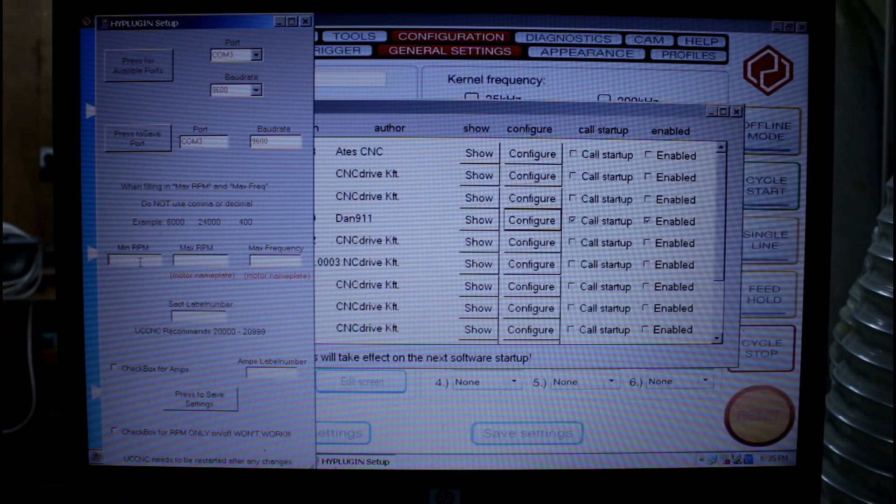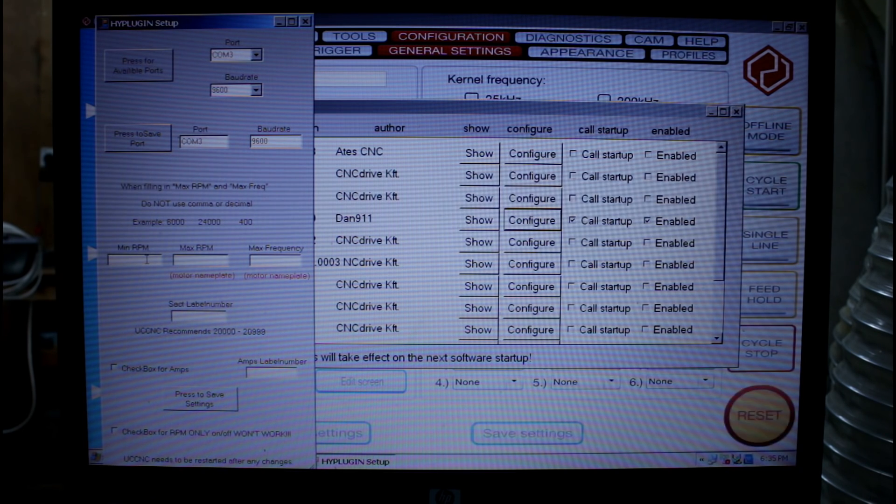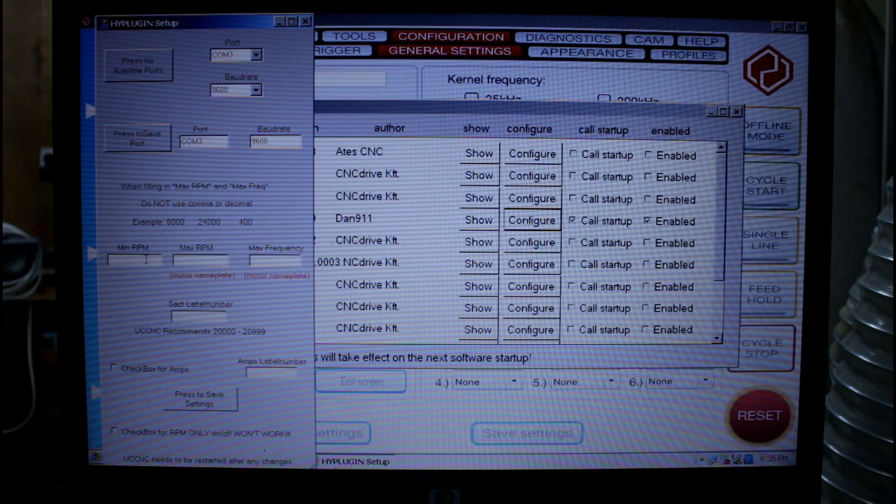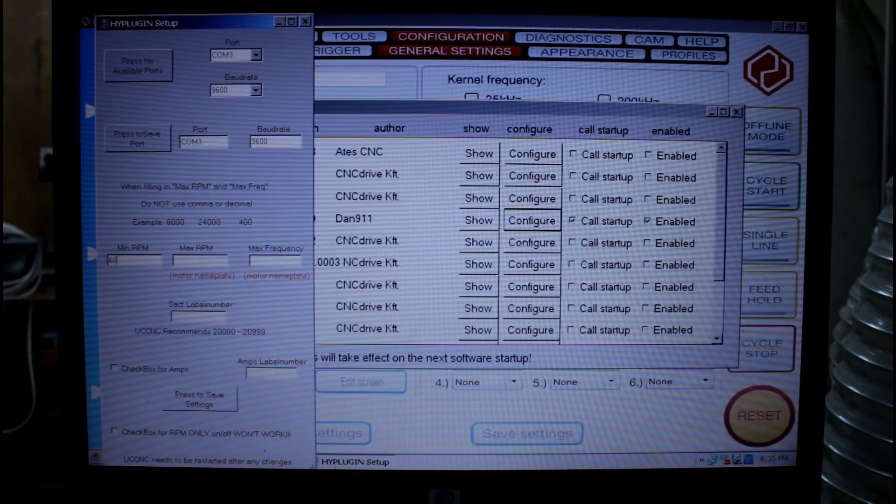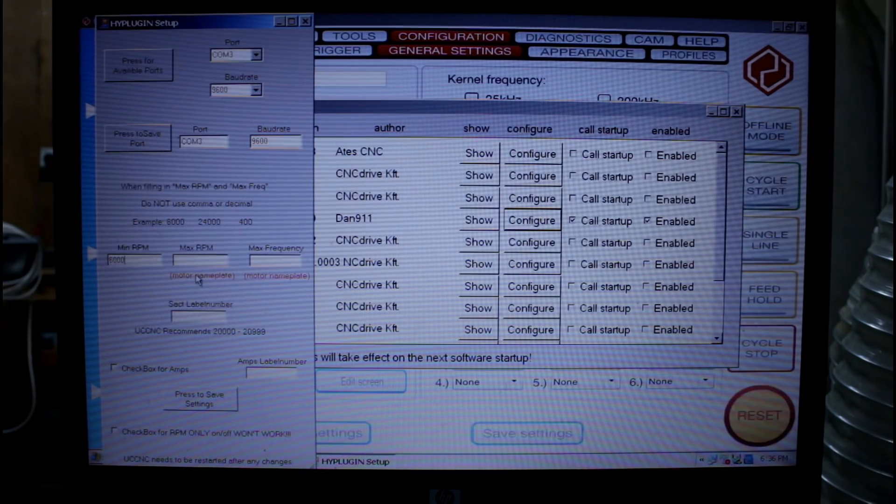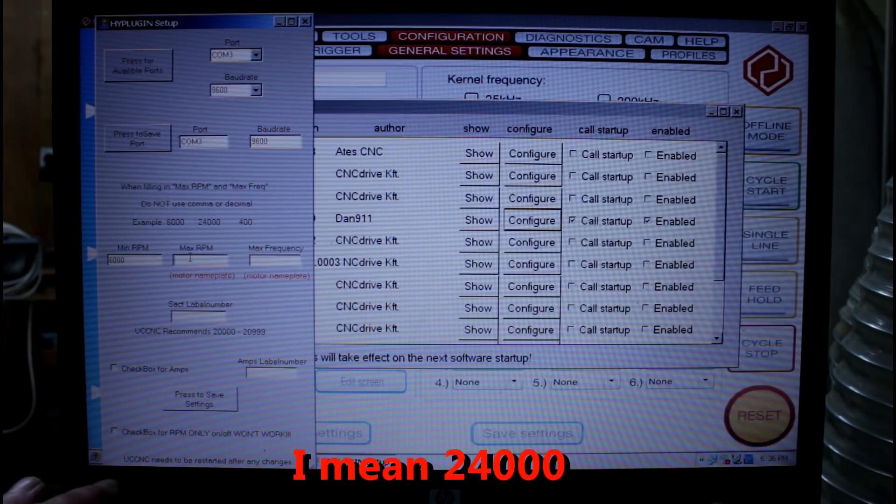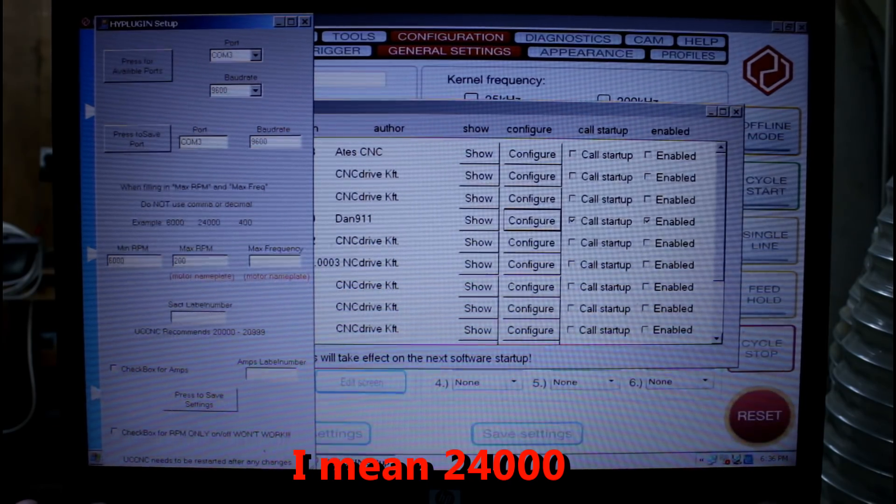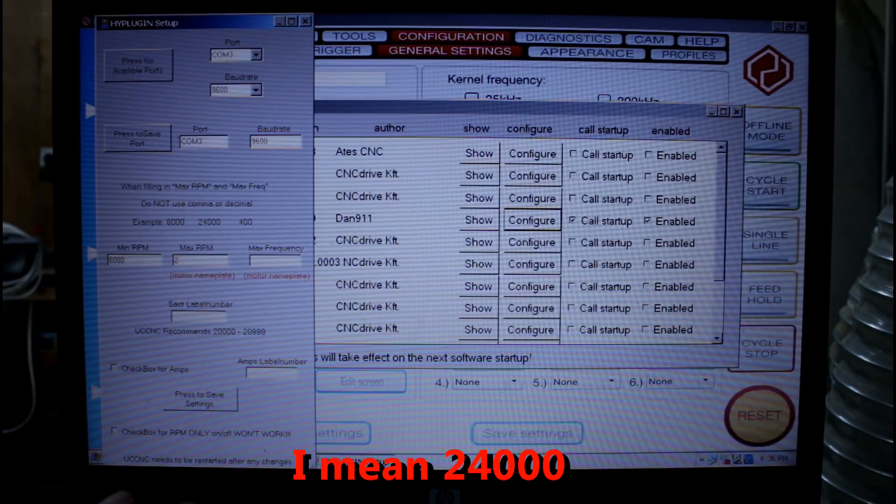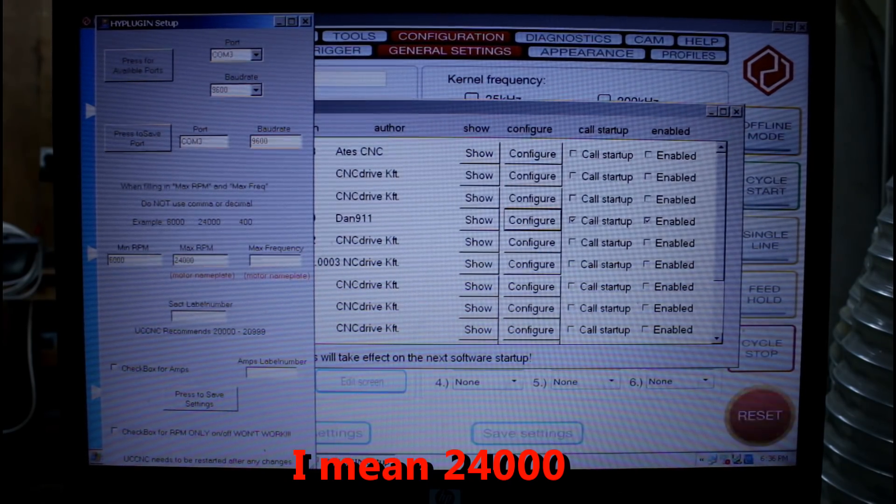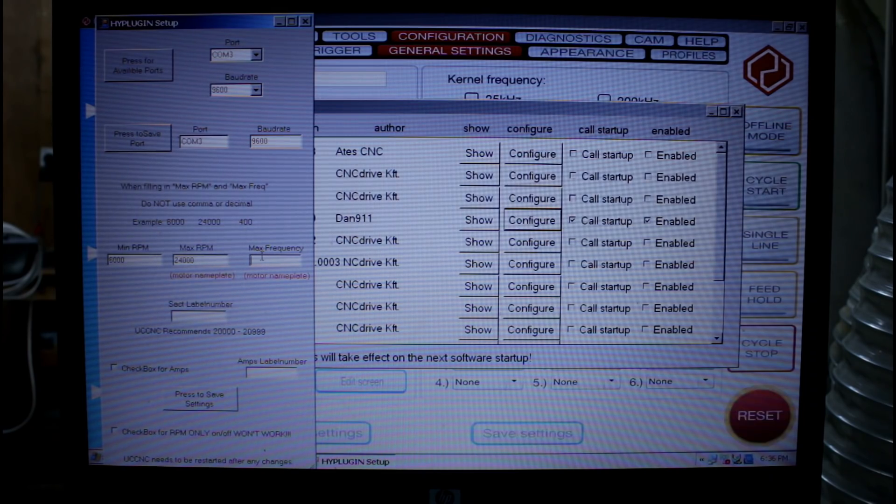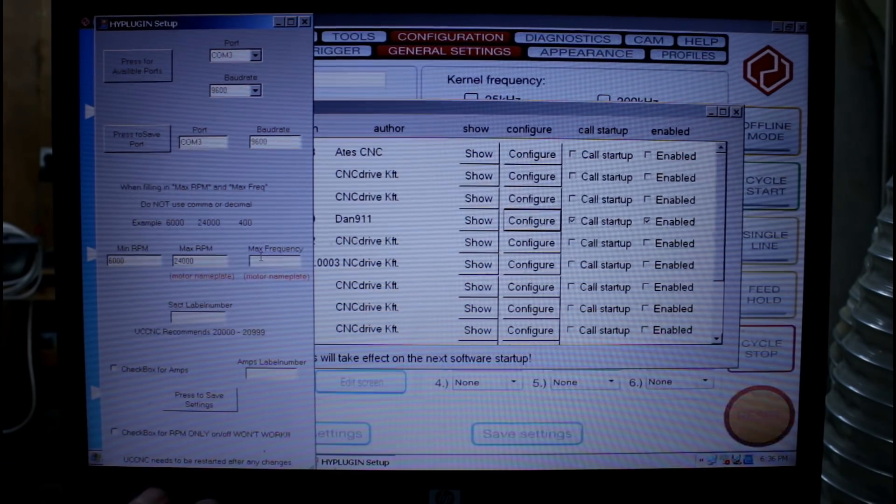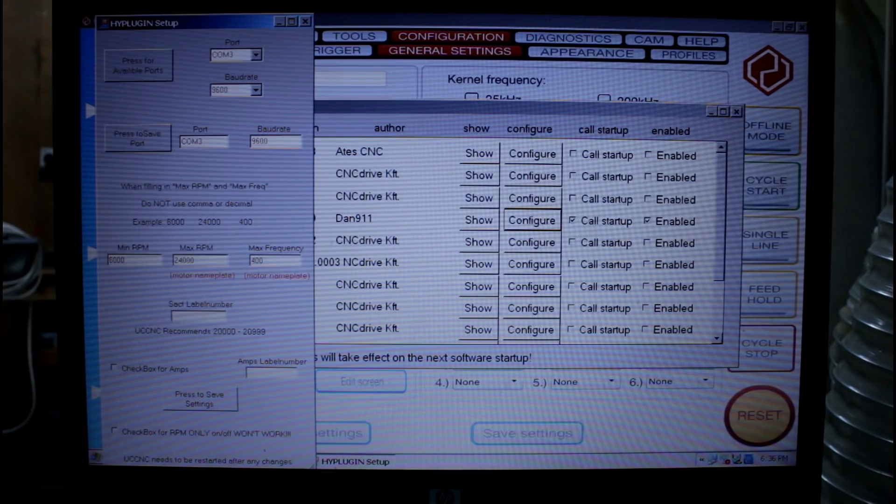Next we need to come down here and set our minimum RPM. In our case 6000. I'm going to have a maximum speed of 24000. That comes from the name plate on the spindle. And the maximum frequency again from the spindle name plate of 400.